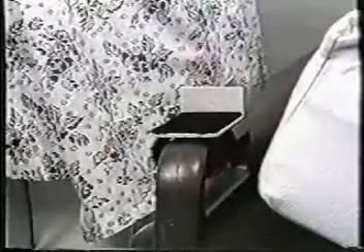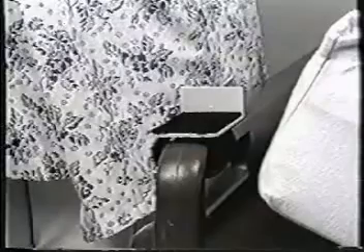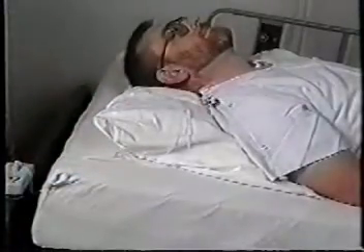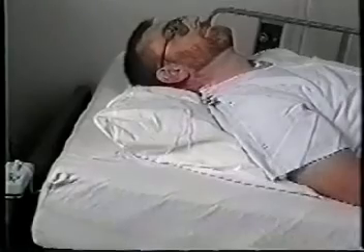To apply the Posey Personal Alarm with the patient in bed or a wheelchair, mount the saddle, the L-shaped holder with Velcro on the long side, in a location where the patient cannot easily reach it, and that allows for some movement without activating the alarm. Mount the alarm box on the saddle. Adjust the cord attached to the magnetic bar to the determined length. Attach the alligator clip to the shoulder or clothing where the patient will not be able to remove it.